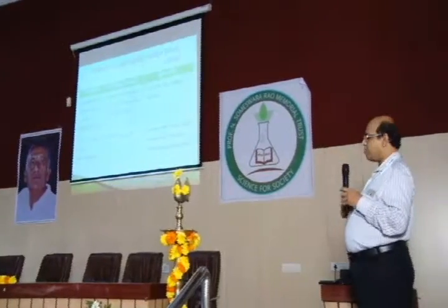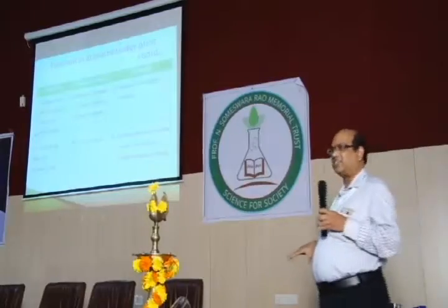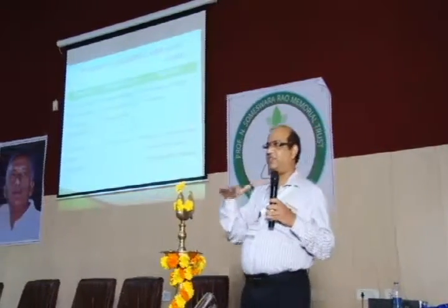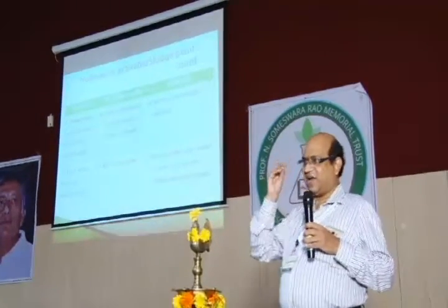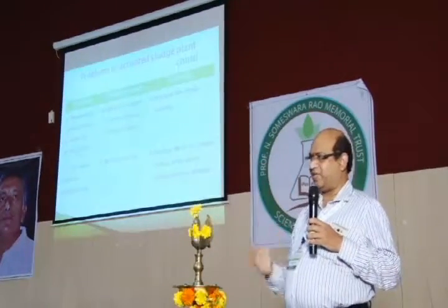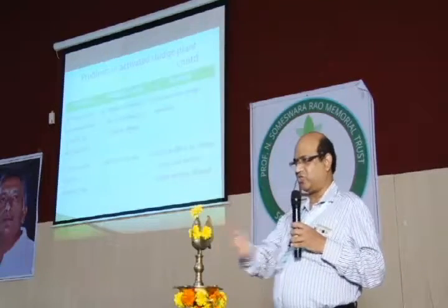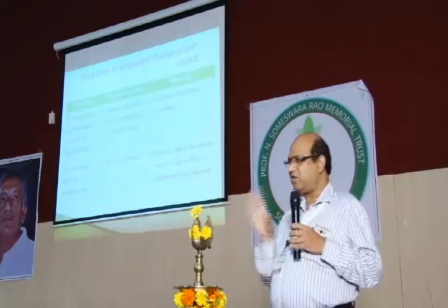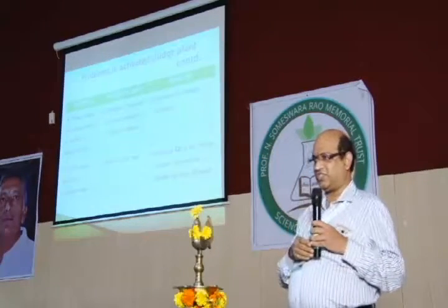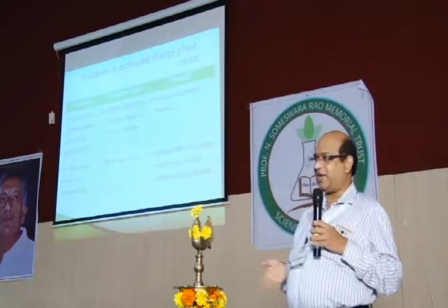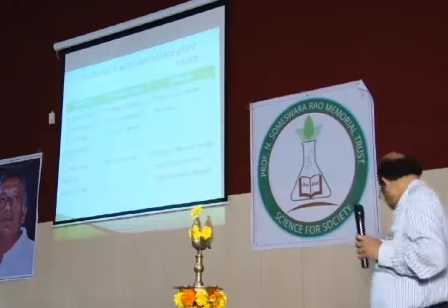Then sometimes white foam is there. Many times white foam appearing means loading is still not sufficient. For example, if the MLSS is designed for 3000 but is only 800 or 1000, a lot of foam issues will be there, though in paper mills and other places surfactants are also one of the issues. But generally, foam appearing means MLSS is still to be developed. Once MLSS is fully developed, ASP can continue.